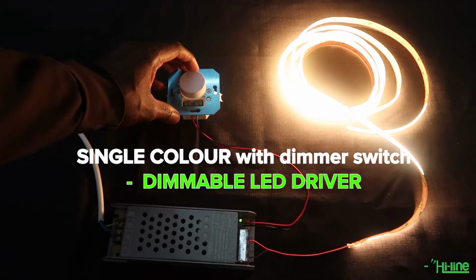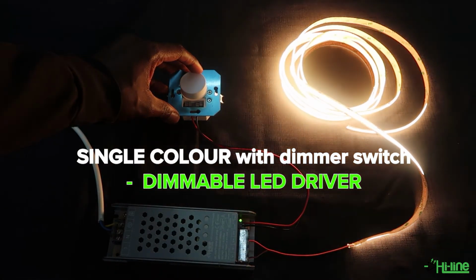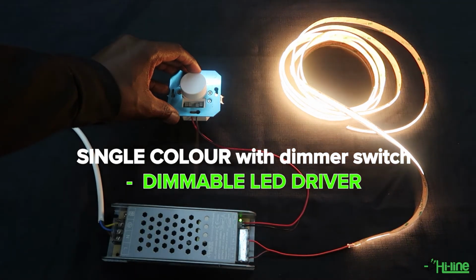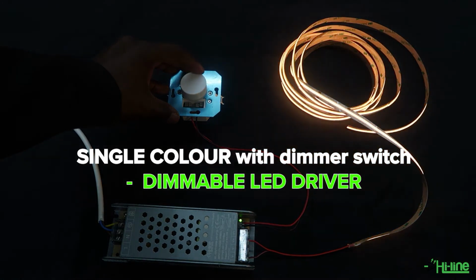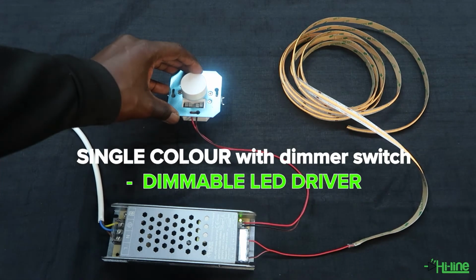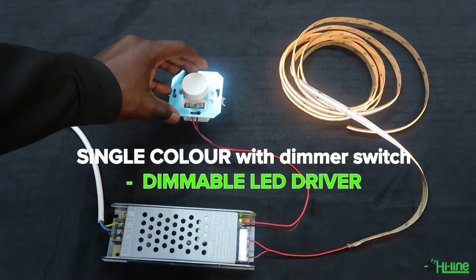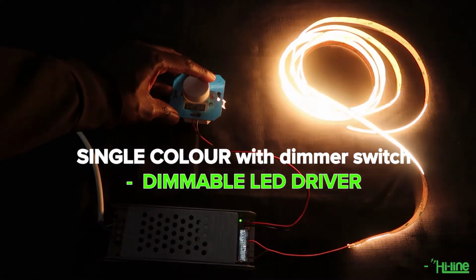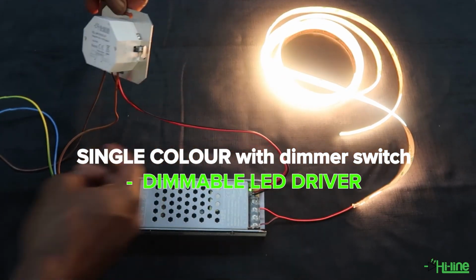But if you'd like to dim the light via a dimmer switch, then in this case you will need a dimmable LED driver instead of a non-dimmable one. In this example, we have our hybrid driver, which can do both leading edge dimming and 0 to 10 volt dimming, like in this case.